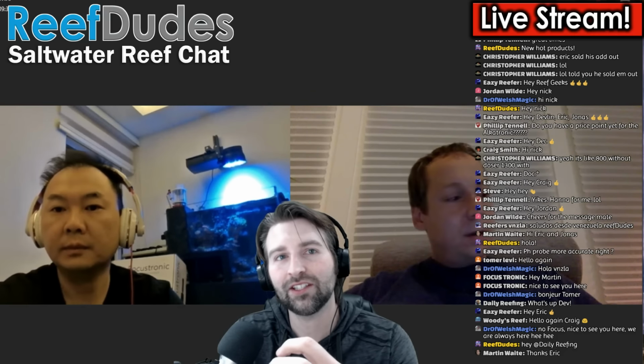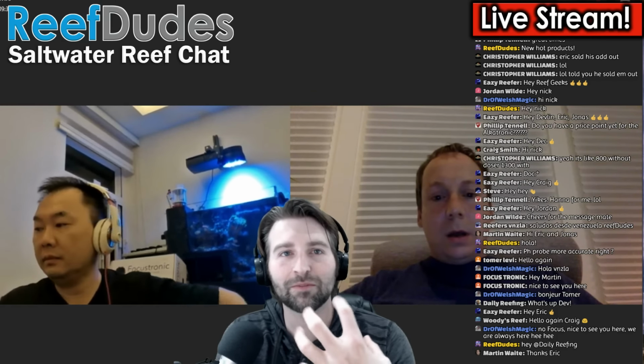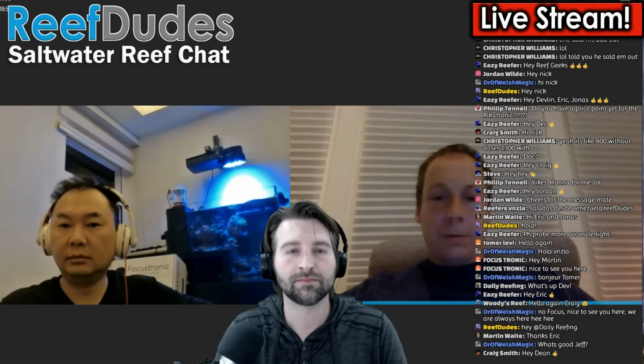No, excellent. Now, for the actual build of it too, so you have stepper motors as well as DC motors inside, correct? Yes. Okay, excellent. And then now, is there any type of maintenance that you need to do on them, or how long are the motors intended to last before you've got to service it or retune it? The service is basically only to change the hoses inside the motors, the peristaltic pump heads. And those hoses will be changed every 6 months for 2 of them and every 12 months for 2 of them. That is basically the service part. Okay, excellent. That doesn't sound too bad.